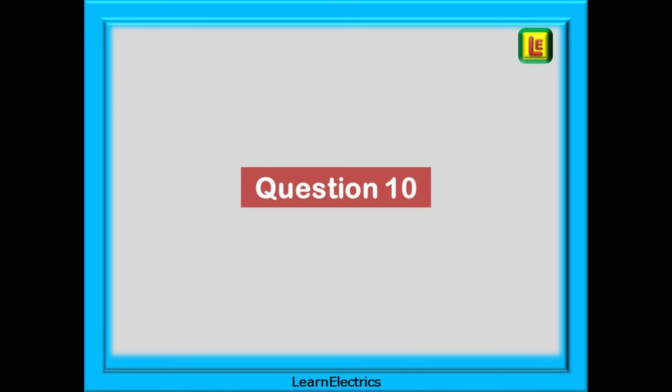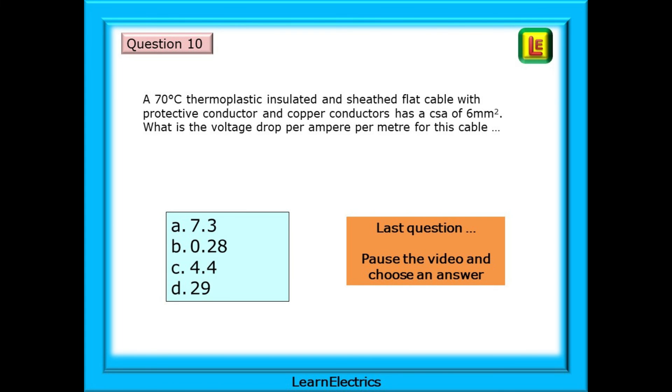And now, question 10. The last question in this help video. A 70 degree Celsius thermoplastic insulated and sheathed flat cable with protective conductor and copper conductors has a CSA of 6 square millimetres. What is the voltage drop per ampere per metre for this cable? There is no calculation to be done. Just find the table and answer the question.